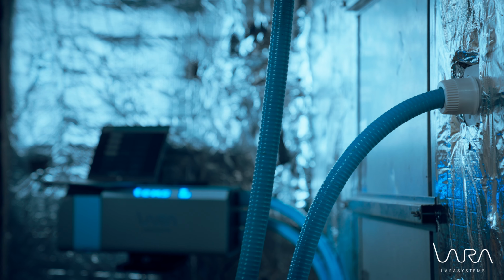If the air duct is equipped with insulation, the insulation around the designated installation point must first be carefully opened up. Create the necessary opening on the air duct at the designated point using the 78 mm hole saw. The supply head is secured to the air duct with a self-tapping screw. After screwing, always check that the head fits properly, does not wobble, and the mounting is secure.